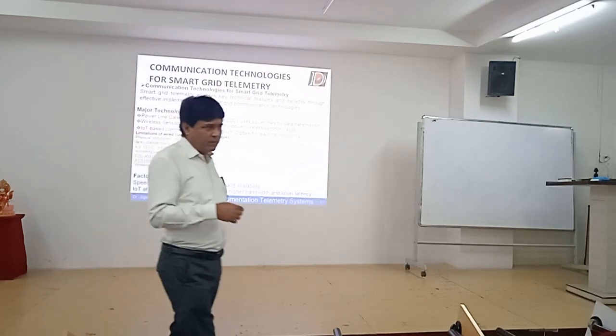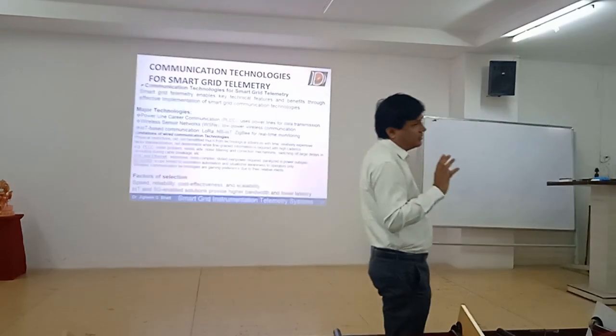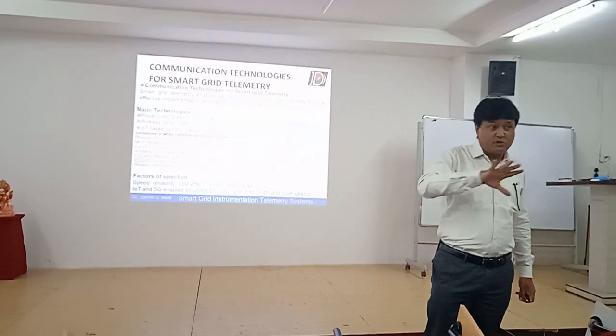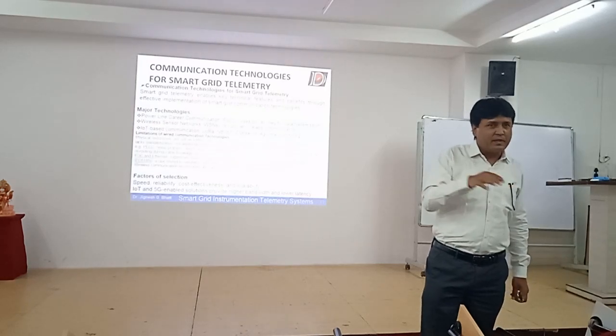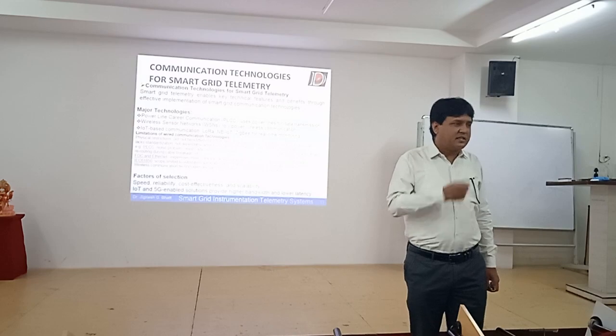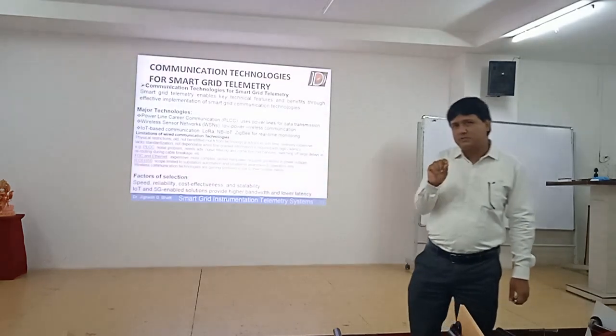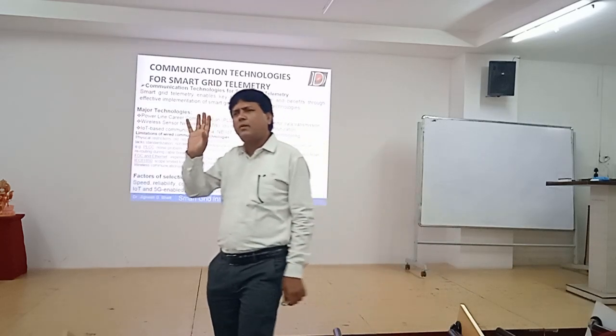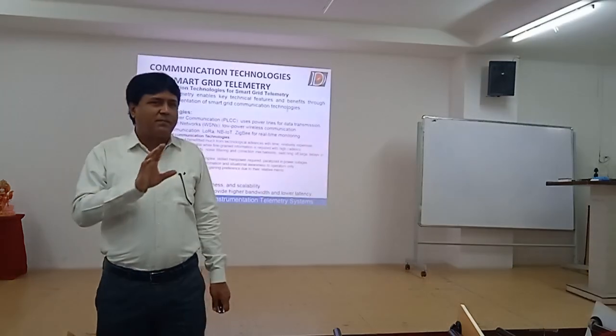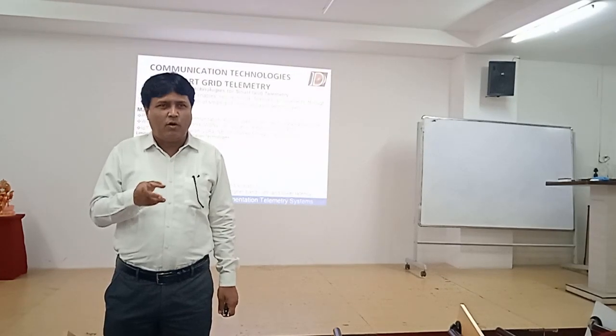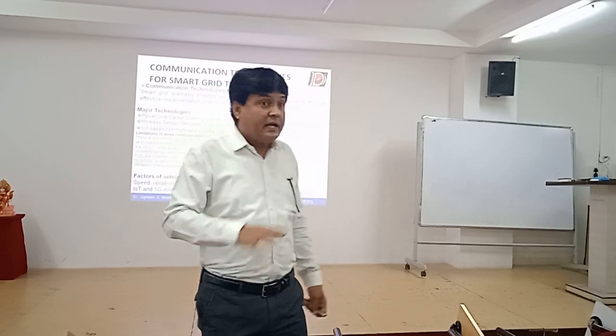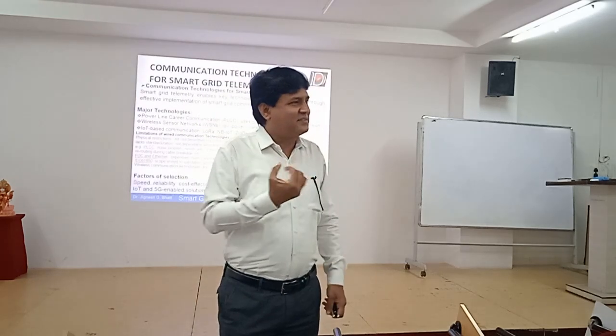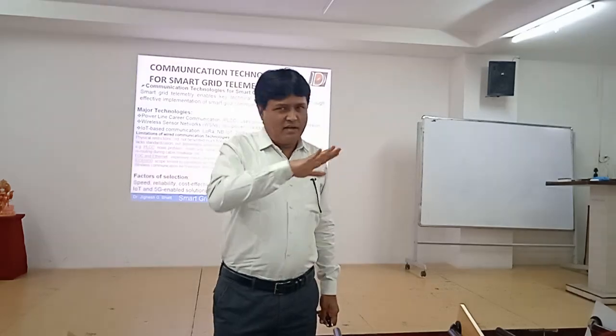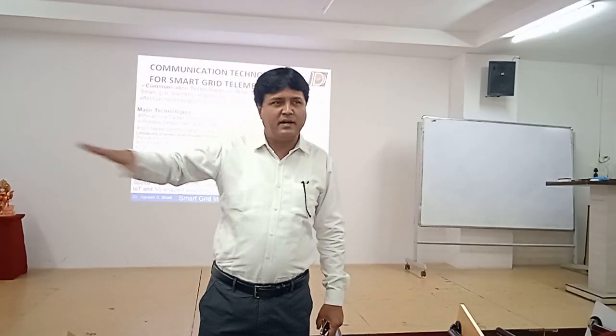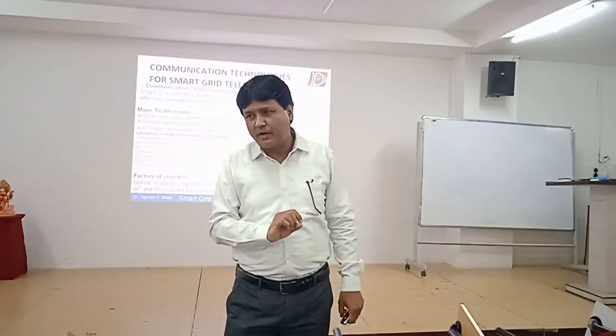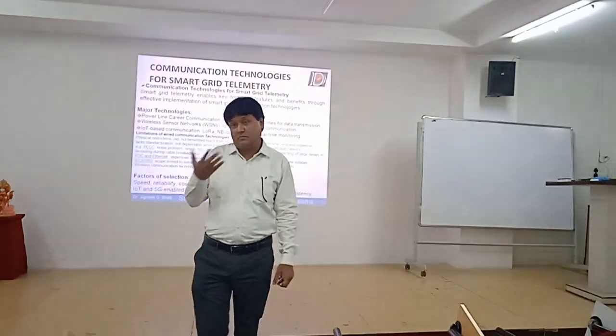In sleep mode, the sensor keeps on working, but the transmitter, which consumes the maximum power in the entire circuitry, goes to sleep mode. Signal conditioning still takes place, and the microprocessor remains live with very low power consumption. As soon as the temperature changes, say by 0.5 degree, it wakes up and starts taking readings. Once readings remain the same for 100 or 200 readings, it goes back to sleep mode, saving a lot of power.